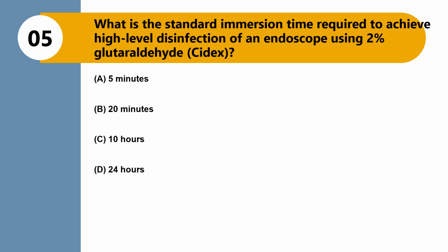Question 5. What is the standard immersion time required to achieve high-level disinfection of an endoscope using 2% glutaraldehyde, Cidex? Option A. 5 minutes. Option B. 20 minutes. Option C. 10 hours. Option D. 24 hours. The correct answer is option B.